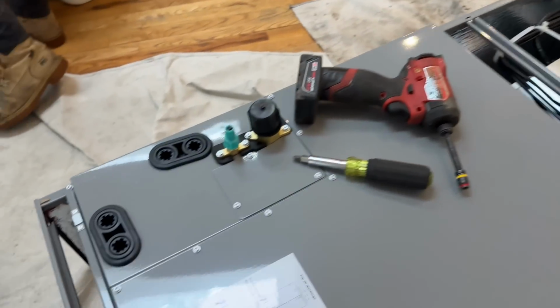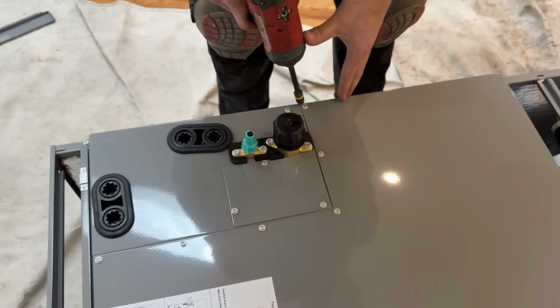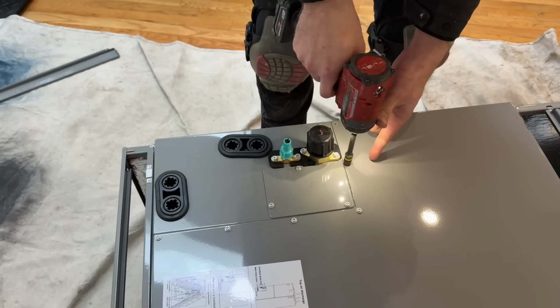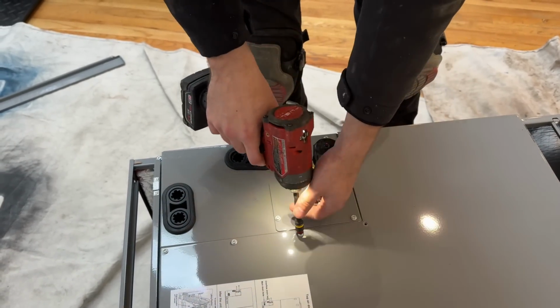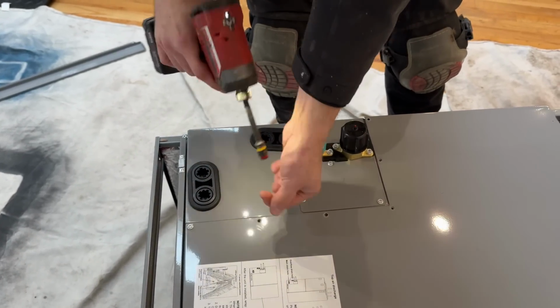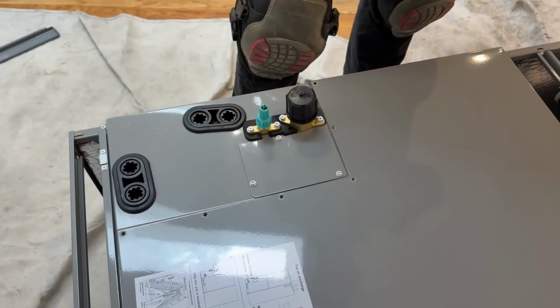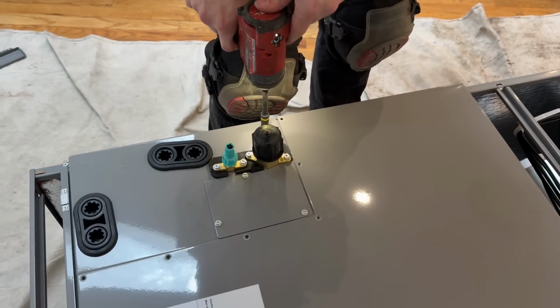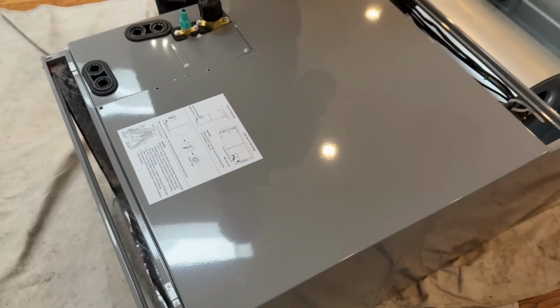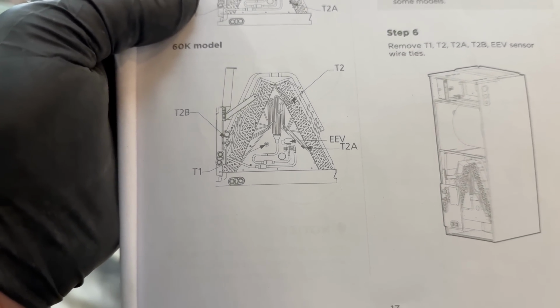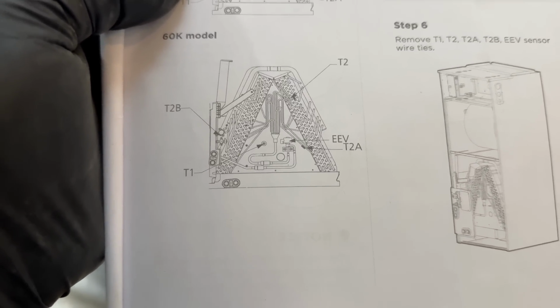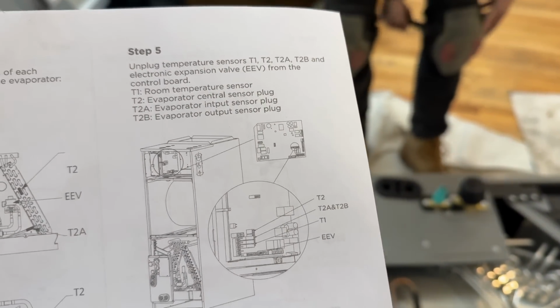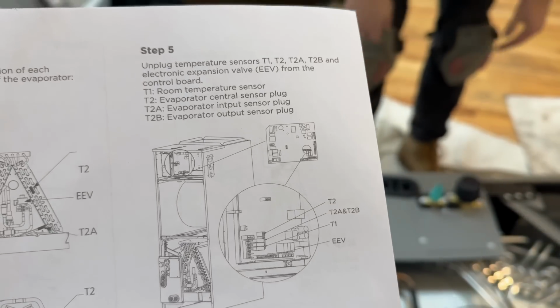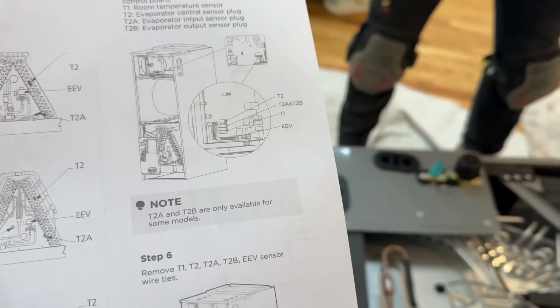Step 3, remove the evaporator cover plate. And we're probably going to have to remove this cover as well. Step 4. Indication of the position of each temperature sensor of the evaporator. We have the 60K model, so we have 4 sensors and the electronic expansion valve. Unplug temperature sensors T1, T2, T2A, T2B, and the electronic expansion valve from the control board.